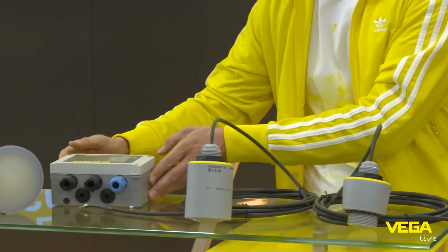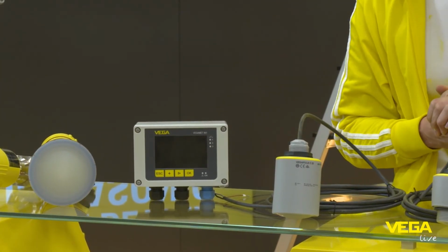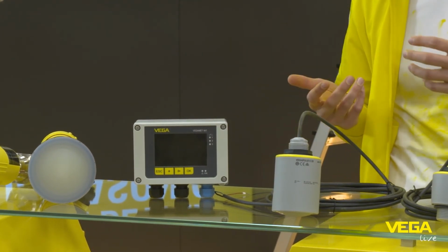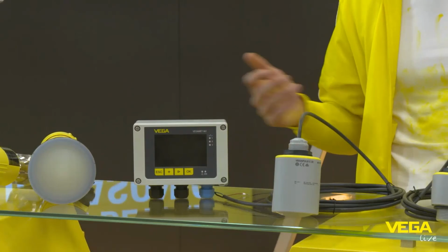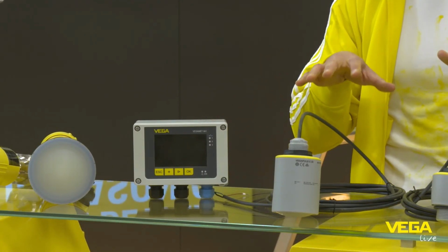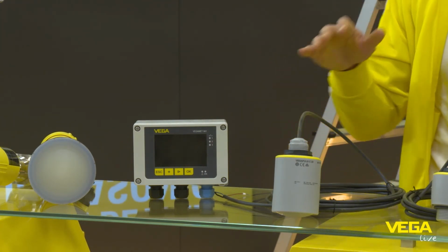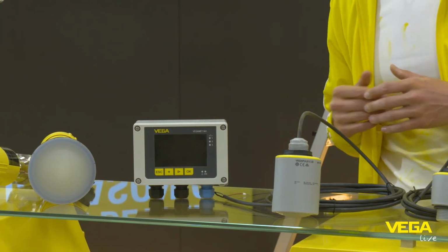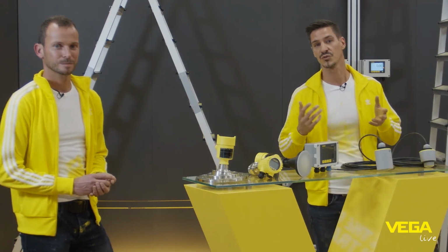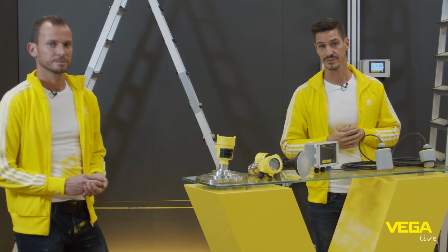As an option, we offer you a new controller, which is called VEGAMET Series 800. You can use this controller to realize simple switching functions, for example, or just as we did it as display. I have to mention it's not mandatory, it's an option. In the past, with ultrasonic transducers, it was mandatory to use a separate controller. With these devices, they can be connected directly to a PLC without any additional controllers. But of course, if you just want to realize a simple switching function, the VEGAMET Series 800 will be the best choice.